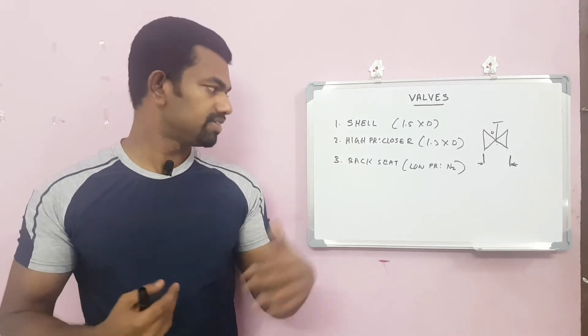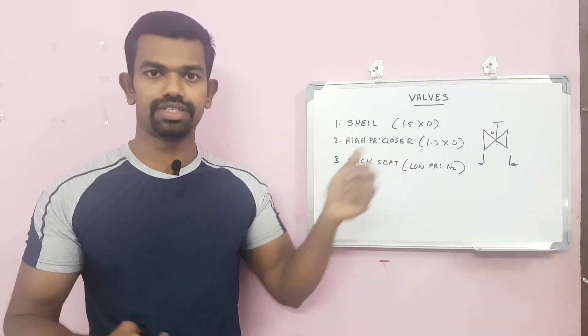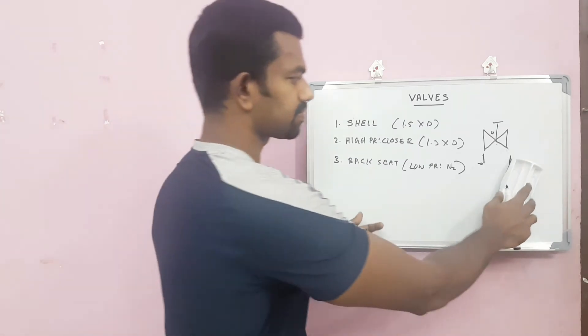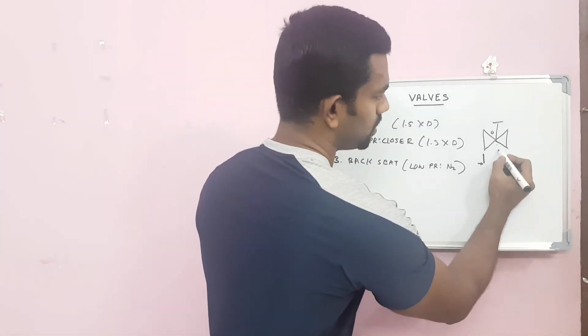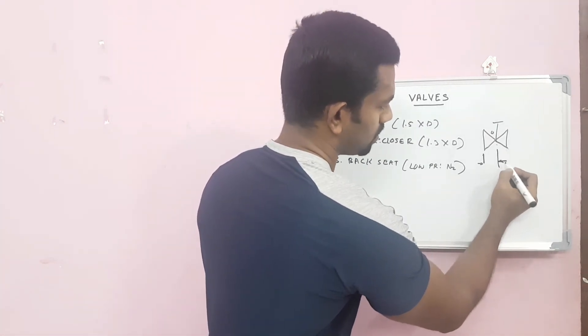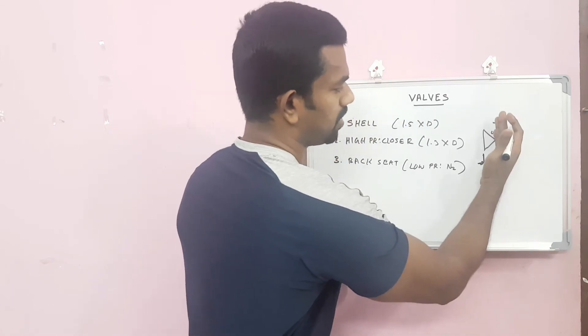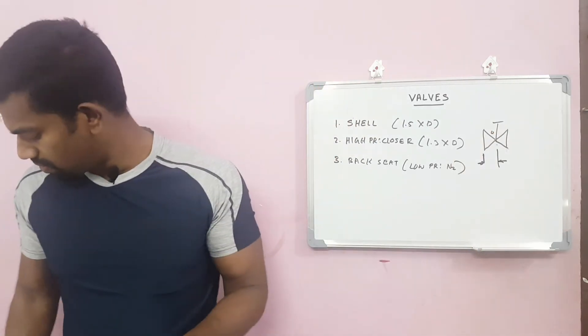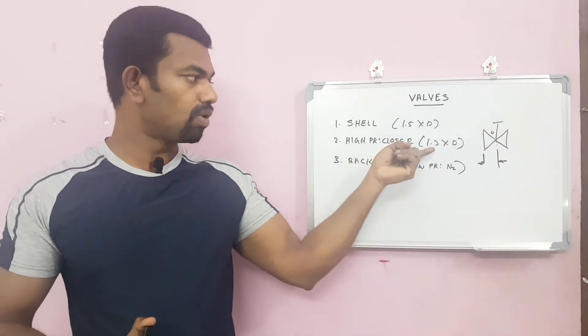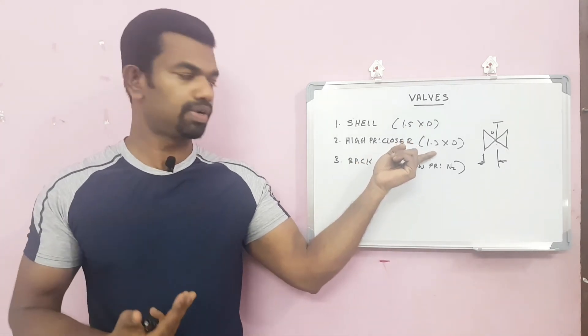Second test is high pressure closure test. In this case, the valve will be closed and we will apply the pressure only on one side with 1.3 times of design pressure.